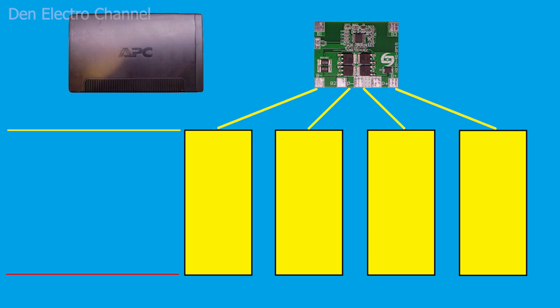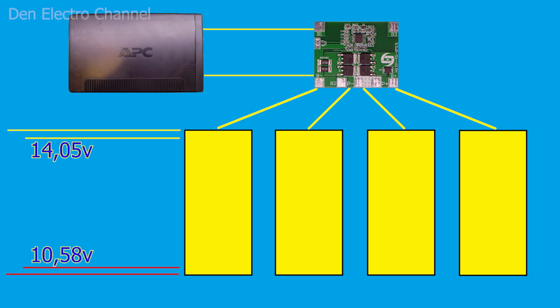When we connect the batteries from the BMS board to an uninterruptible power supply, the rules change a little. The UPS charged its battery to a voltage of 14.05 volts, and it turned off when the battery voltage dropped to 10.58 volts. The uninterruptible power supply works according to its own system — it will only see the total voltage coming out of the BMS board, it cannot see the voltage of each individual battery. It turns out it will turn off charging when the total voltage of all batteries reaches 14 volts.